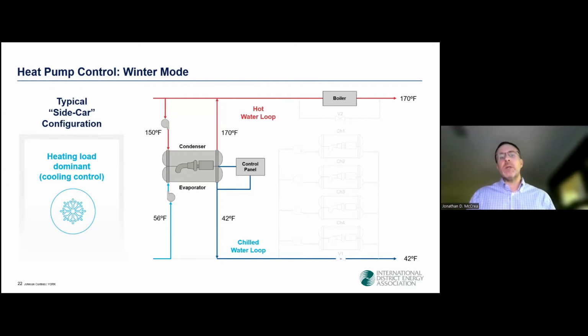But it could be anywhere. It could just be in any place in your system where the heat pump can be connected to both of those loops. So as you can see, the system is operating with a 170-degree supply hot water temperature and a 20-degree delta T, and the chilled water is 56 to 42. And in this scenario, it's wintertime, so there's a relatively small cooling load in the system and a much larger heating load.